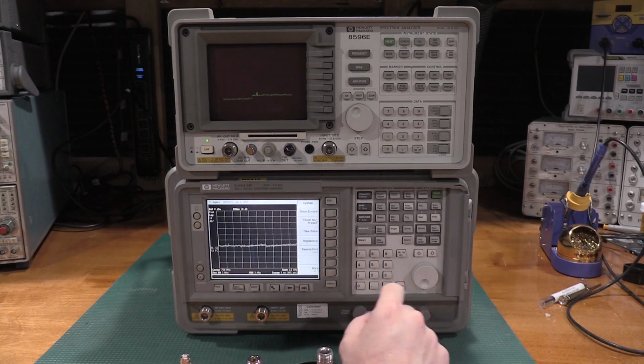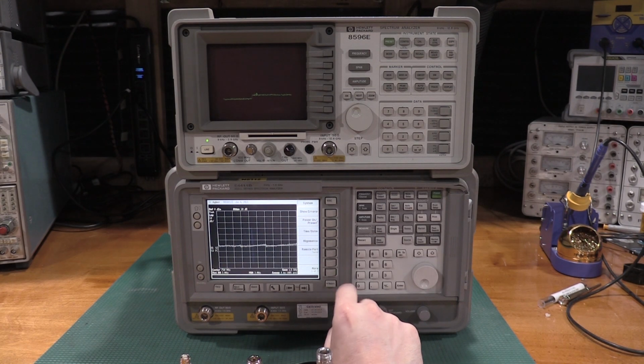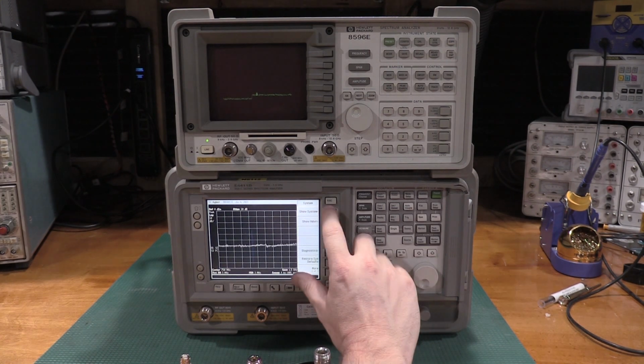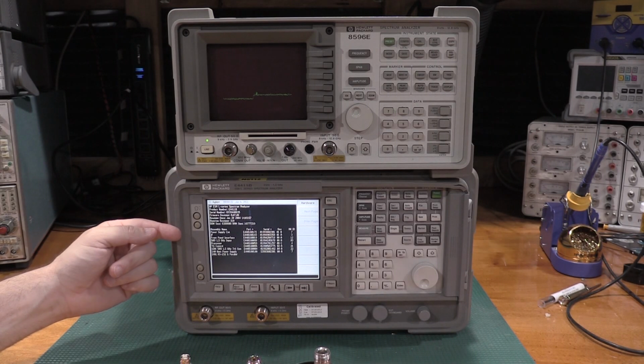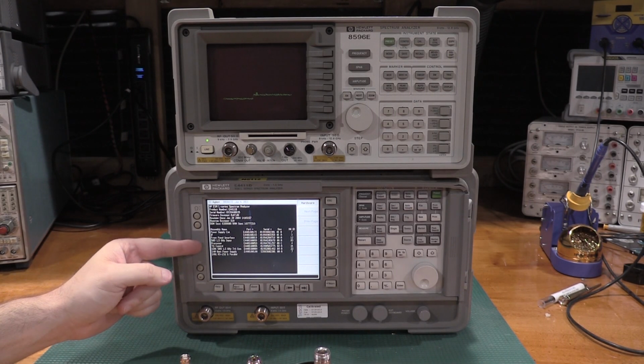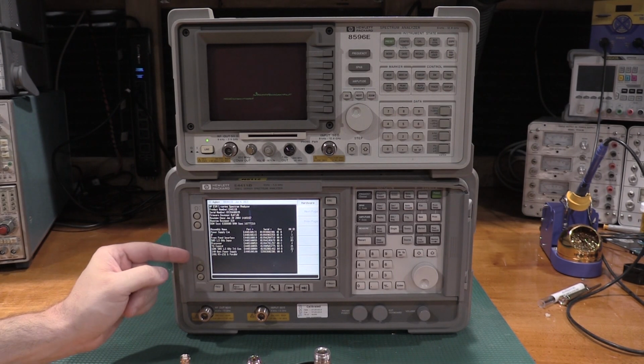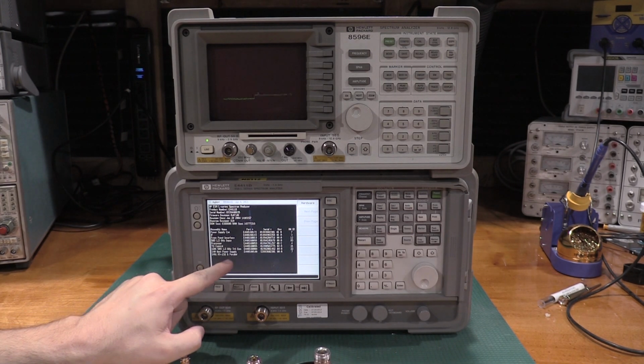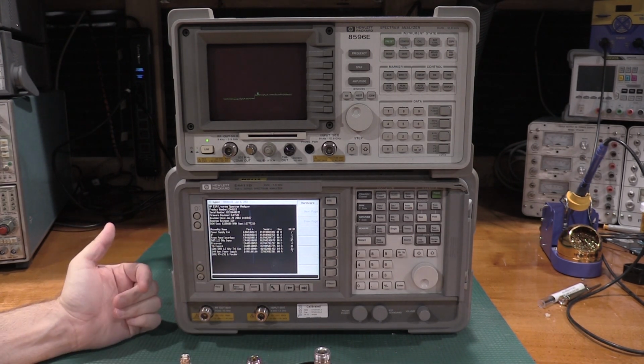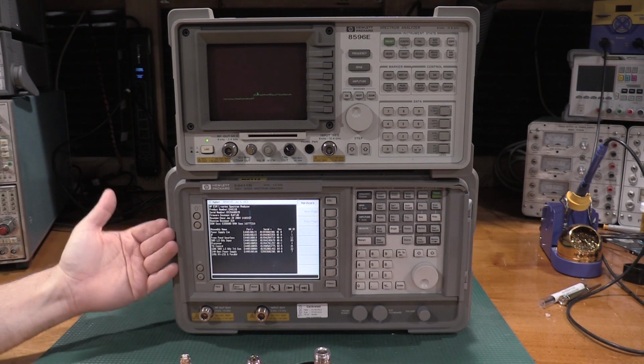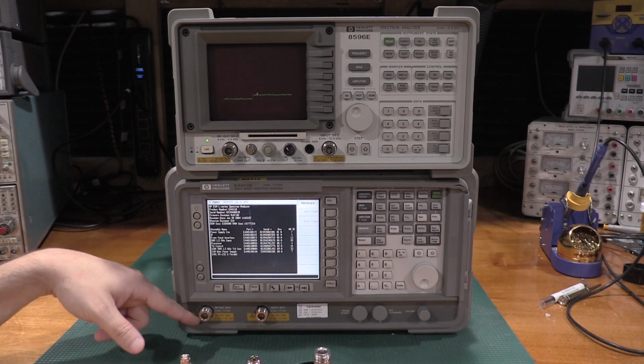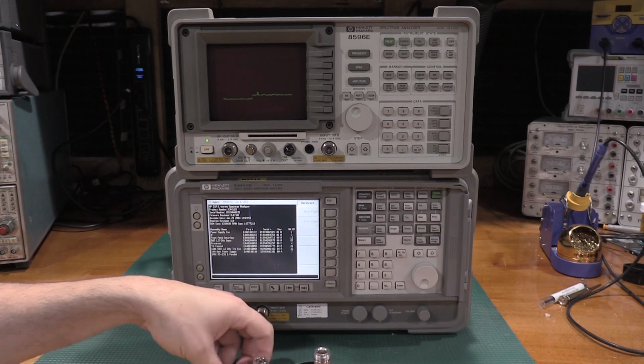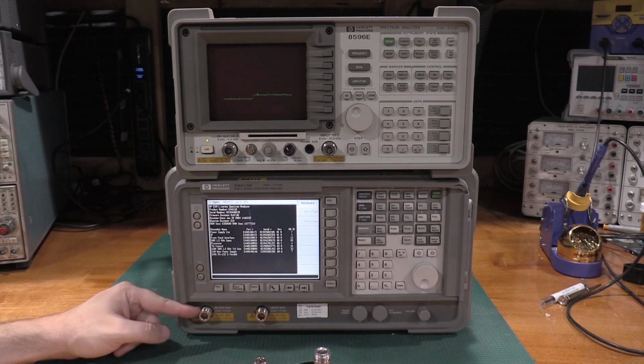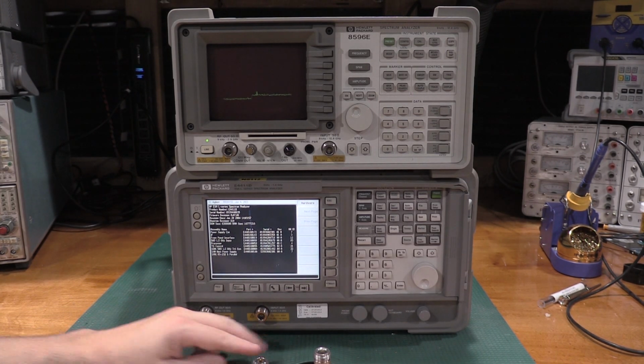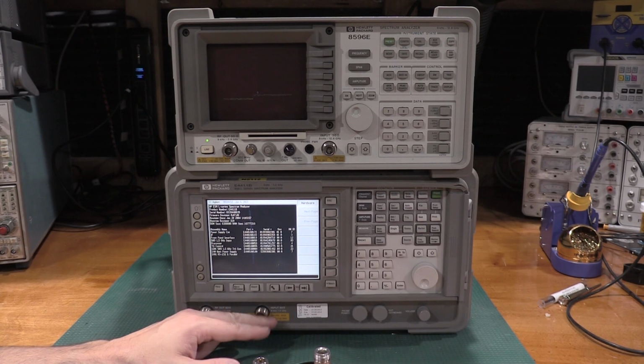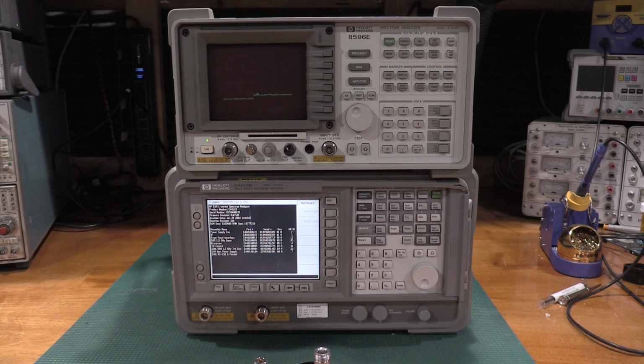We can take a look at the options if we go to System and Show System, or Show Hardware. As we can see, we have tracking generator control, we have the tracking generator, and this one actually has the RS-232 and parallel port option on it. So the main reason for picking this up was the full speed tracking generator for this one, which goes up to 1.5 gigahertz, and having the input that can be very abused and not die.